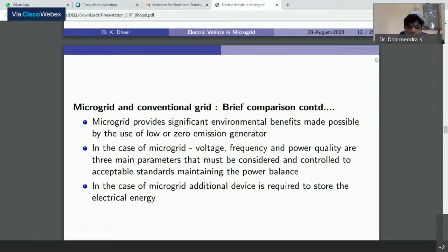And in a microgrid, voltage, frequency, and power quality are three main parameters that must be considered and controlled within acceptable standards, maintaining the power balance. This is a challenge, and in an islanded microgrid it is a greater challenge. When it is connected to the main grid, the voltage and frequency will be dictated by the main grid, and power quality can be maintained. If there is some harmonic load, that much harmonic current will be taken from the grid. So these issues are more in islanded mode in comparison to grid connected mode.